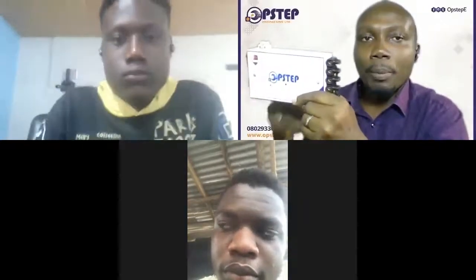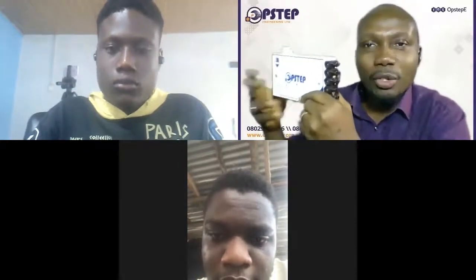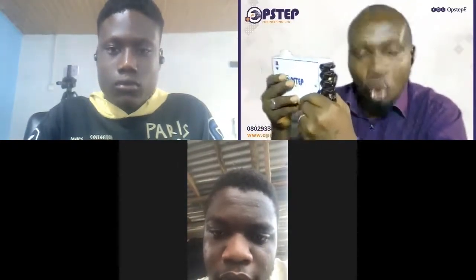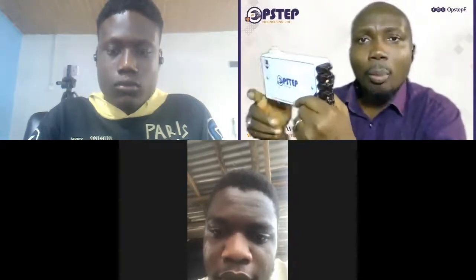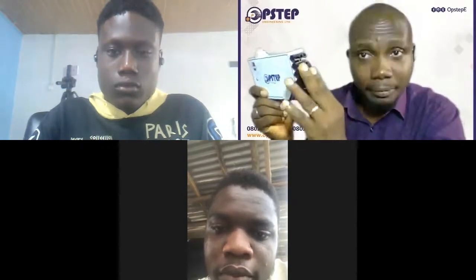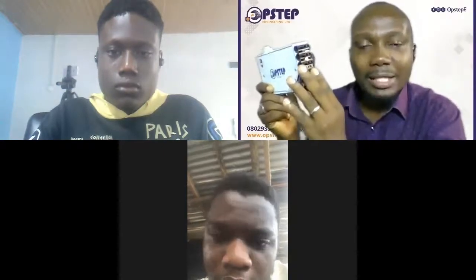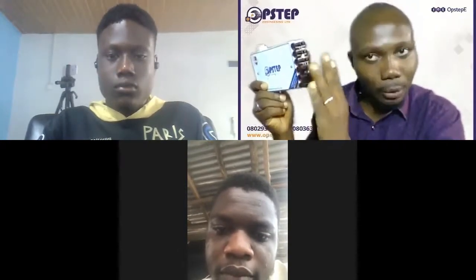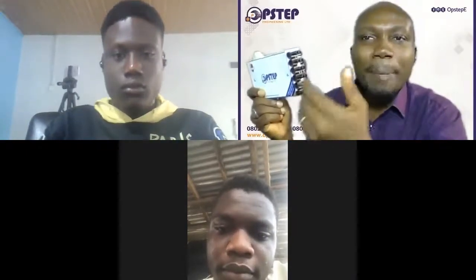For you to operate your manual changeover switch, you have to go and turn on your generator and then switch to your generator inputs. But in the case of the automatic changeover switch, of course you have to turn on your generator, but you do not need to switch anything here. This system will recognize the presence of your generator and automatically place the house on that generator input. That's what it does.